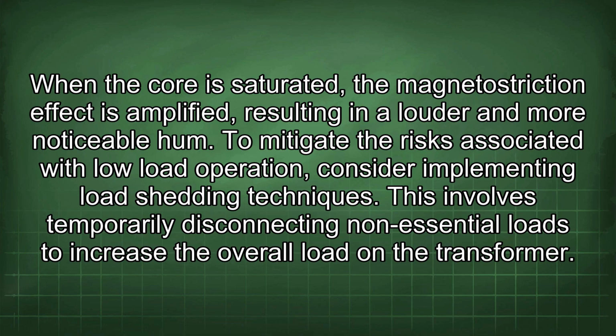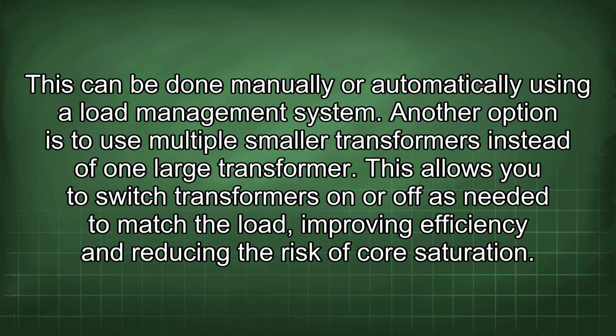To mitigate the risks associated with low load operation, consider implementing load shedding techniques. This involves temporarily disconnecting non-essential loads to increase the overall load in the transformer. This can be done manually or automatically using a load management system.